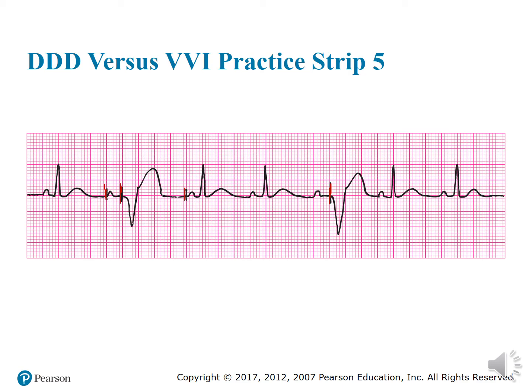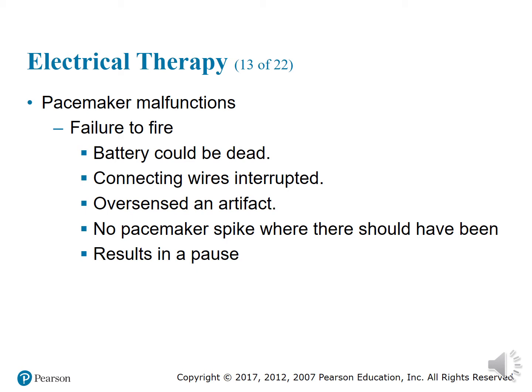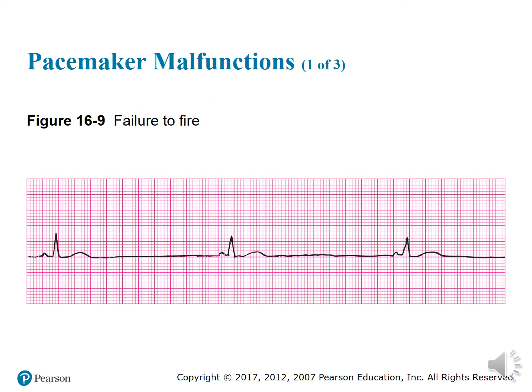So let's move on. All right. So we got pacemaker malfunctions that failed to fire. The battery could be dead. Connecting wires are interrupted. Oversensing and artifact. No pacemaker spikes where they should have been. Results in a pause. We kind of see next in those strips that we just looked at, where the pacemaker wasn't going off where it should be. All right, so this is what it looks like when it failed to fire. Look back, that's actually what the first practice strip that we just went over looked like.